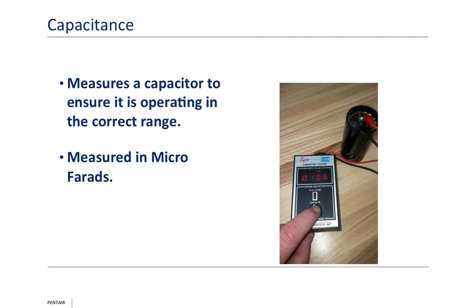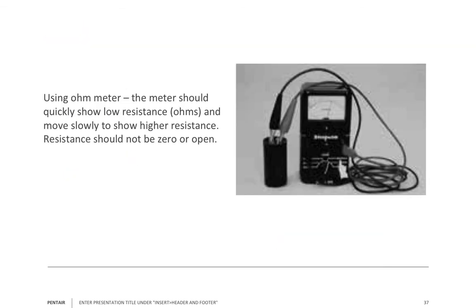Capacitance, we already talked about that. We want to get a solid number. On this device here, that capacitor is rated for 86, but it's measuring 105. So it's measuring high, but that's okay for a start capacitor.